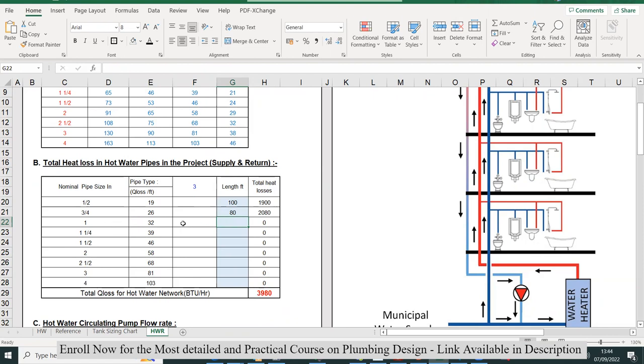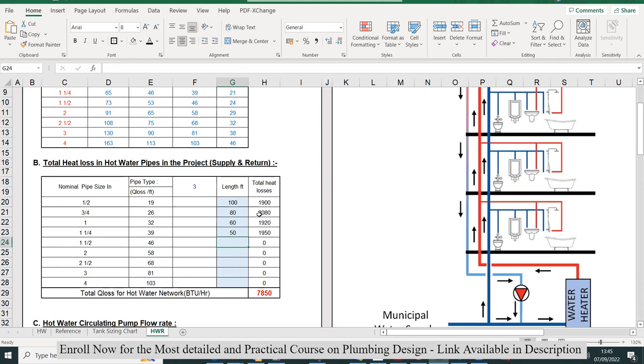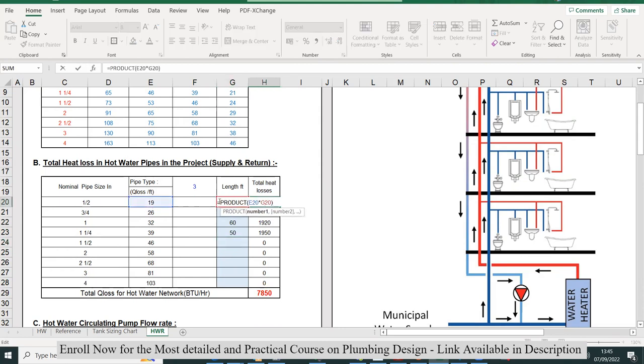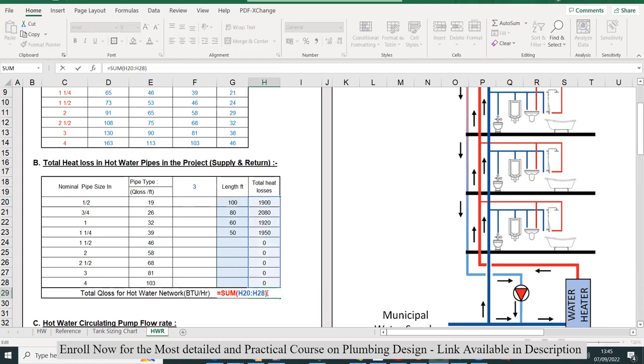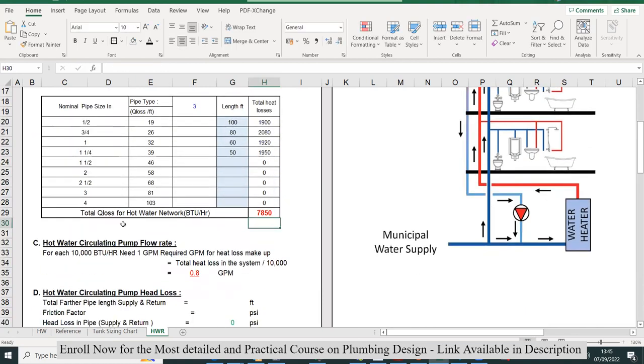For one inch, it's 60 feet, and for one and a quarter, let's say it's 50 feet. Half will be supply, half will be return. You have to add the total supply and return. Once you multiply these losses with the total length in feet, you'll get the total losses. When you add all this, you get the total heat loss in the hot water network—that's 7,850 BTU per hour.